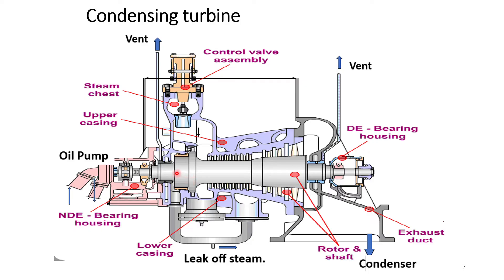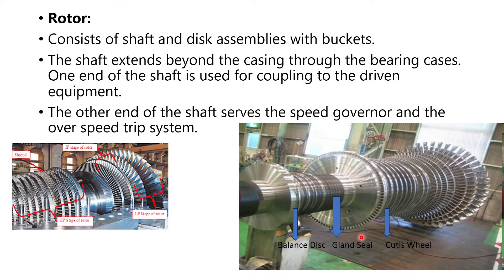One more thing we can see here is the leak-off line. What happens is when the steam comes on the balance disk, the pressure is much higher there, and a part of that steam through a leak-off line is bypassed to some lower stage of the turbine where it does some work to drive the rotors. This is the rotor shaft and these are all the rotor blades.